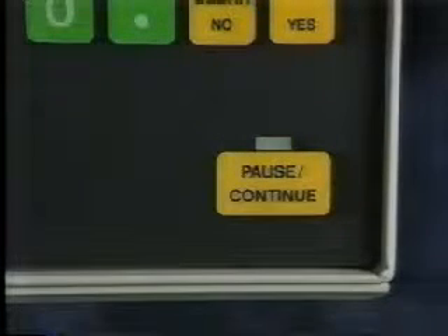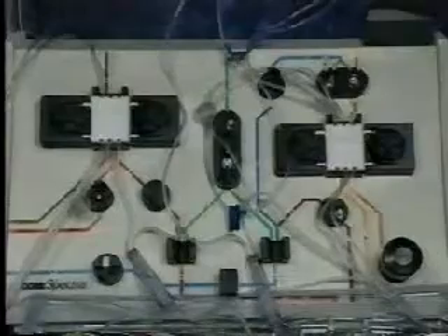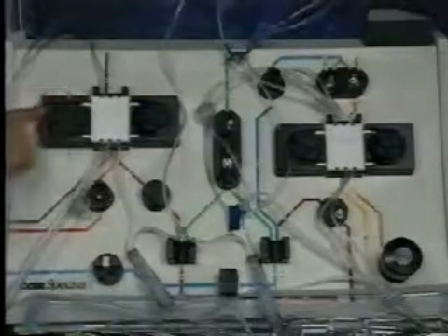Then, press the Continue key on the display panel to load the tubing onto the pumps. Notice that the cartridge clamps will automatically retract and the tubing is threaded onto the pump rotors. The valves will open to the load position. Verify that the pumps are loaded and visually check for kinked tubing in the pump rotors.